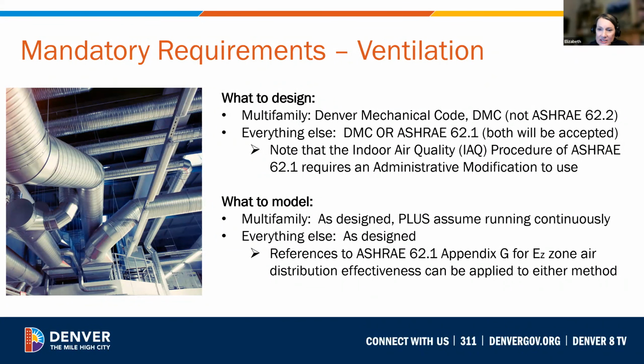For the designers, when designing ventilation for multifamily residential projects, make sure you follow the Denver Mechanical Code, not ASHRAE 62.2. Then for all other commercial spaces, the ventilation procedure in Chapter 4 of the Denver Mechanical Code should be used since it's our adopted code. However, the ventilation procedure in Section 403 of the Denver Mechanical Code is almost identical to the ventilation procedure in 6.2 of ASHRAE 62.1. So Denver will accept either Denver Mechanical Code 403 or the ventilation rate procedure in 6.2 of ASHRAE 62.1 to demonstrate code compliance for ventilation. Now, if you would like to use the indoor air quality procedure in 6.3 of ASHRAE 62.1, that can work too, but you will require an administrative modification to use it.